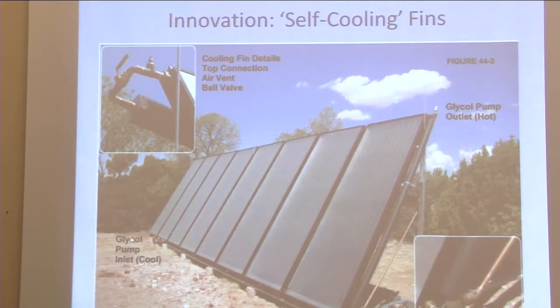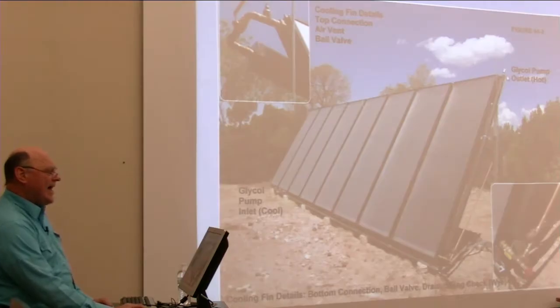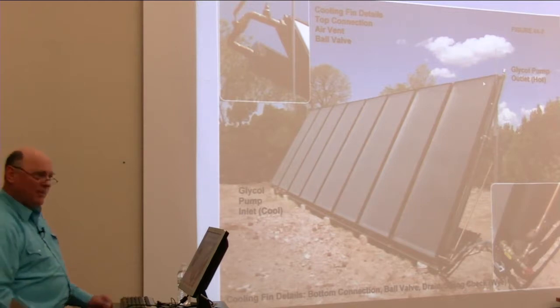So normally, during normal operation, you would pump into the bottom corner, pump the glycol through the collectors until it was hot, and it comes out the top and back down to the house. That's normally when the pump is on. Well, when the pump is off, let's say during a power failure, where will the heat go? First, the liquid in the collectors will rise by natural convection because as it gets hotter, heated by the sun, it becomes less dense, tends to expand and rise. So the hottest fluid starts rising and builds up in this header at the top of the collectors. It can't go out where the pump would pump it because the pump's not running.